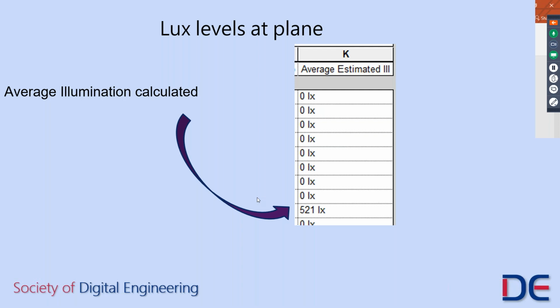The estimated lighting load calculated here is probably a bit rough and ready. It's not going to be as accurate as if you do it in Dialux or Relux, for example. But it does give us a kind of running commentary on how close we are to what our desired goal will be. And for a simple object like this meeting room, this is actually fairly good. It's fairly accurate. More complex spaces and more complex lighting schemes, we'll probably need to refer to more specialist software to calculate the true values.